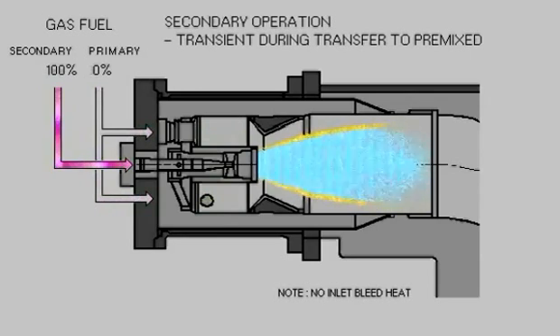This mode is a transition state between Lean-Lean and premix modes. This mode is necessary to extinguish the flame in the primary zone before fuel is reintroduced into what becomes the primary pre-mixing zone.